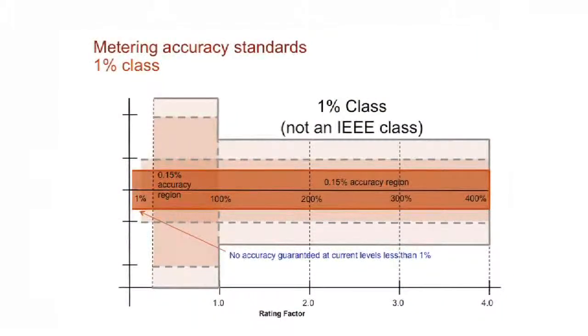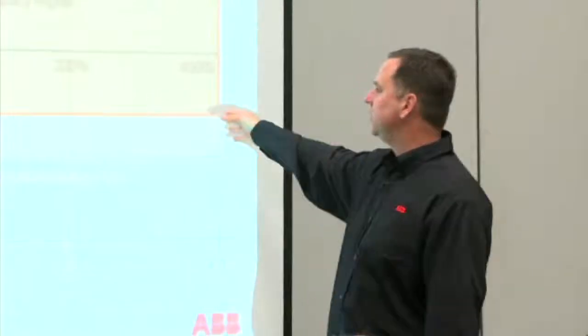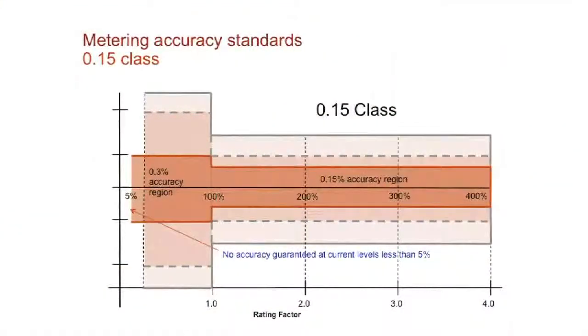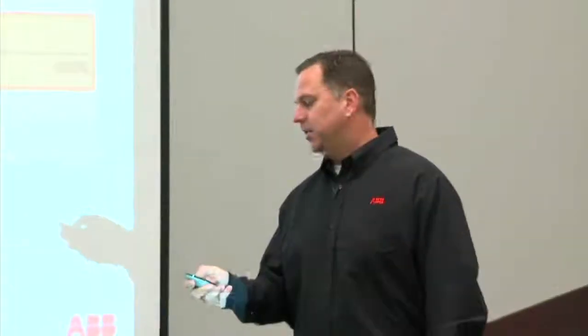Okay, we get to revenue class accuracy, you can see that the bandwidth starts to narrow a little bit, where from 100% of nominal current through your rating factor, you go down to 0.3%. But as you get into lower load applications, as your current decreases, the accuracy falls off in a current transformer. Our 0.15 class, again, narrows that bandwidth down. Anything above your nominal current will be at 0.15%. So your CTs will be more accurate, therefore your meter will be more accurate. But again, as you fall down below your nominal current, as you start getting to low loads, your accuracy is allowed to fall off again by double to 0.3%. Still much more accurate than the revenue class, but not the most accurate that's out there.